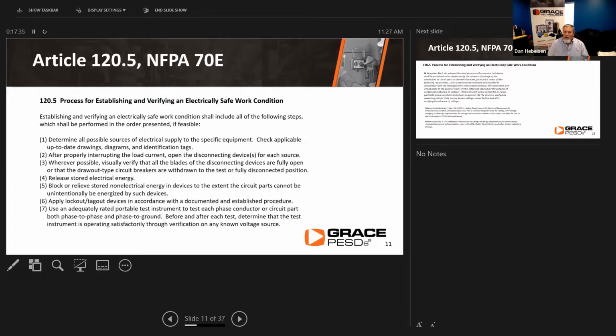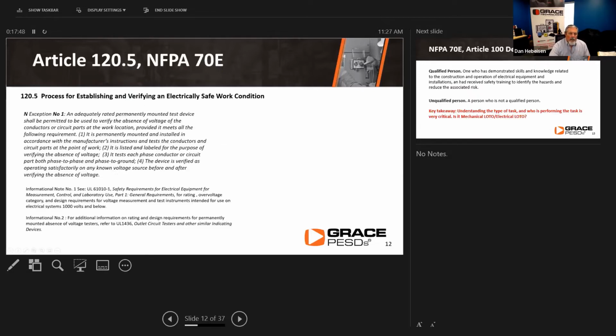So you're going to start at a known source, check your meter, verify it's working, do the measurements, verify that there is no energy, and then go back and recheck your meter. So live, dead, live on the test equipment. Article 120.5 under NFPA 70E has made some changes in the last several years. And this, as we just discussed, is the process for establishing and verifying the electrically safe work condition.